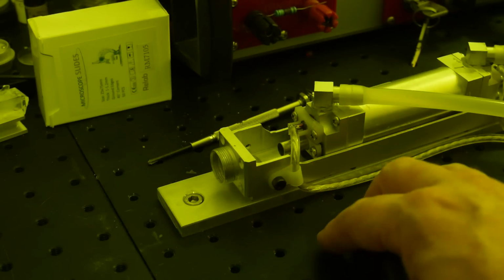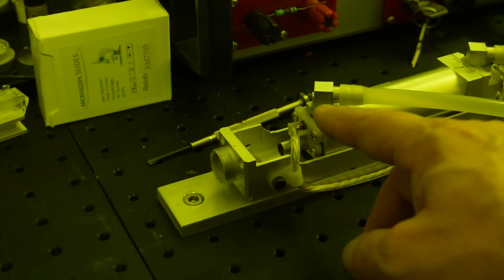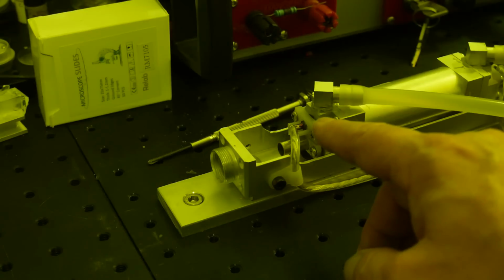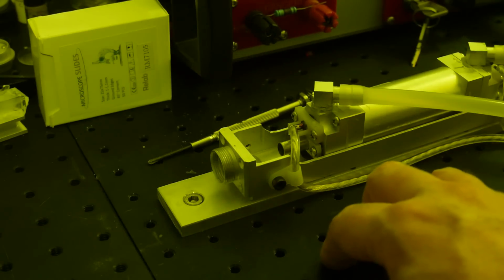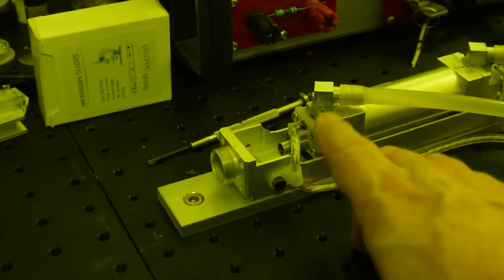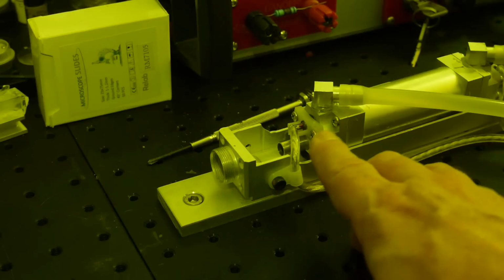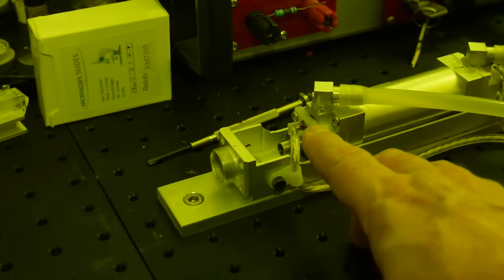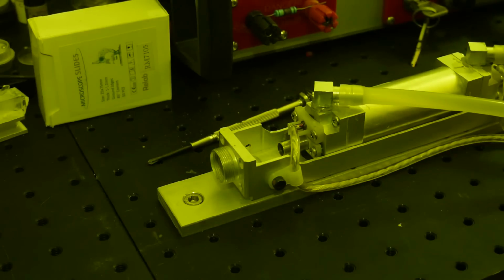There shouldn't be any more light being emitted. But what's actually happening is we get to fire it a couple of times, and then it seems to strike an arc inside the flash lamp itself, which is definitely not good for the flash lamp. It'll cook the flash lamp to the point where the whole thing explodes. So let's see that actually happen. Hopefully I can do this without the thing eating itself, but I'll turn the power supply on and we'll have a look.